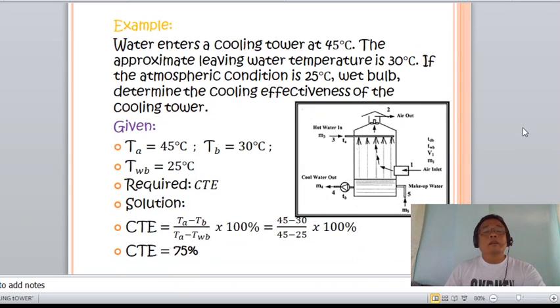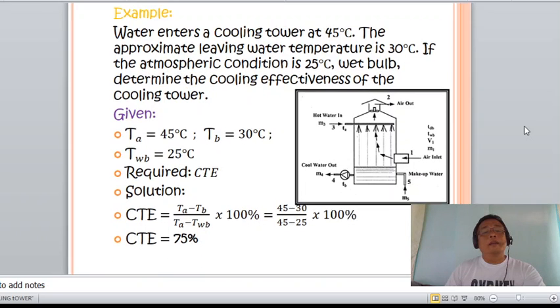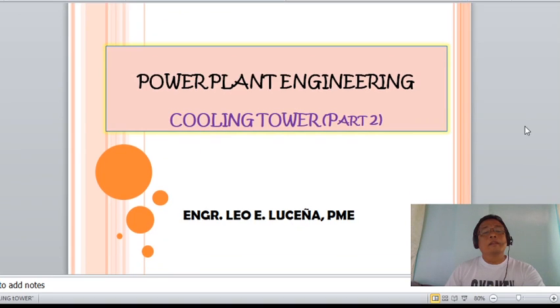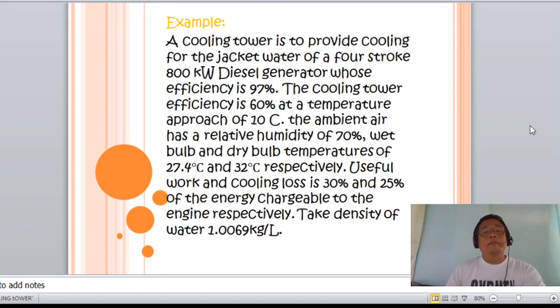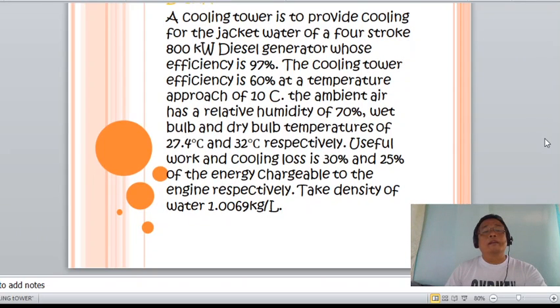Okay? So let us again consider another example. We have here a cooling tower to provide cooling for jacket water for a 4-stroke 800 kilowatt diesel generator whose efficiency is 97%. Cooling tower efficiency is 60% at a temperature approach of 10. The ambient air has a relative humidity of 70%, wet bulb and dry bulb temperatures of 27.4 and 32 degrees Celsius respectively. Useful work and cooling loss is 30% and 25% of the energy chargeable to the engine respectively. Take density of water as 1.0069 kilogram per liter.